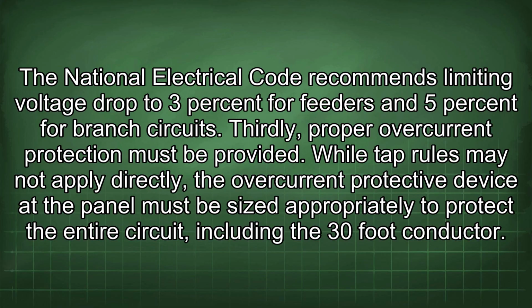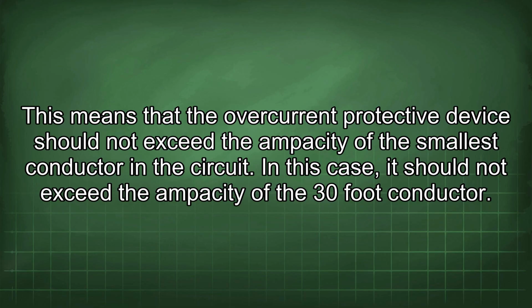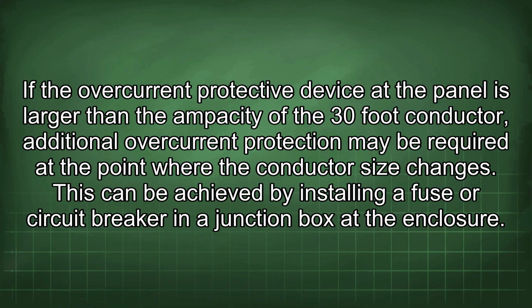Thirdly, proper overcurrent protection must be provided. While tap rules may not apply directly, the overcurrent protective device at the panel must be sized appropriately to protect the entire circuit, including the 30-foot conductor. This means that the overcurrent protective device should not exceed the ampacity of the smallest conductor in the circuit. In this case, it should not exceed the ampacity of the 30-foot conductor. If the overcurrent protective device at the panel is larger than the ampacity of the 30-foot conductor, additional overcurrent protection may be required at the point where the conductor size changes. This can be achieved by installing a fuse or circuit breaker in the junction box at the enclosure.